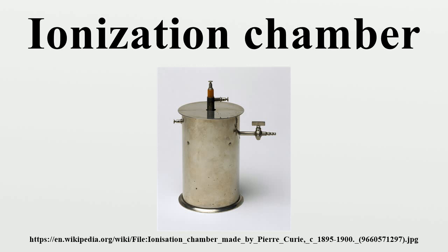Since then, the ion chamber has been a widely used tool in the laboratory for research and calibration purposes. To do this, a wide variety of bespoke chamber shapes, some using liquids as the ionized medium, have been evolved and used. Ion chambers are used by national laboratories to calibrate primary standards, and also to transfer these standards to other calibration facilities. Handheld ion chambers are widely used in handheld radiation survey meters to measure beta and gamma radiation. They are particularly preferred for high dose rate measurements, and for gamma radiation they give good accuracy for energies above 50 to 100 keV.